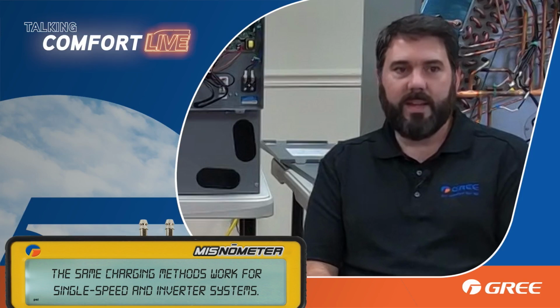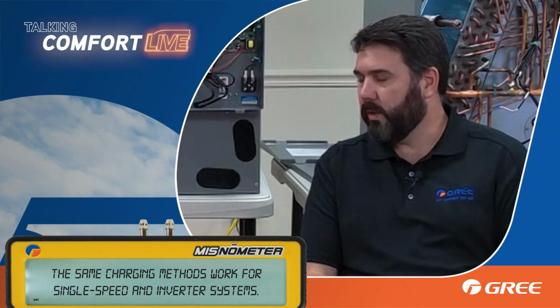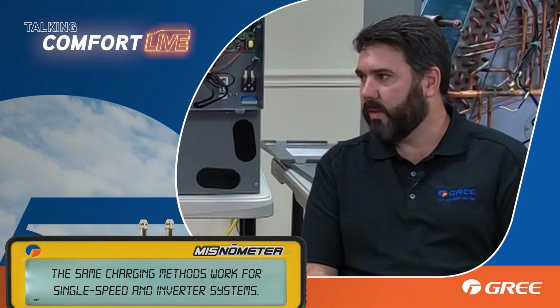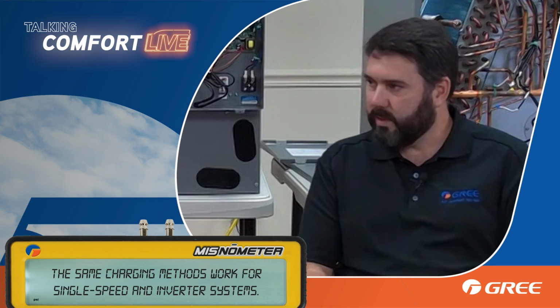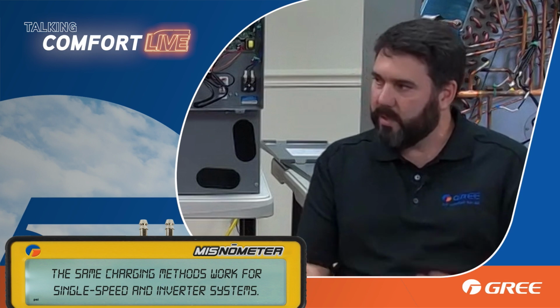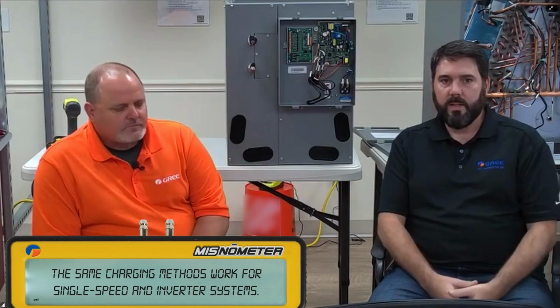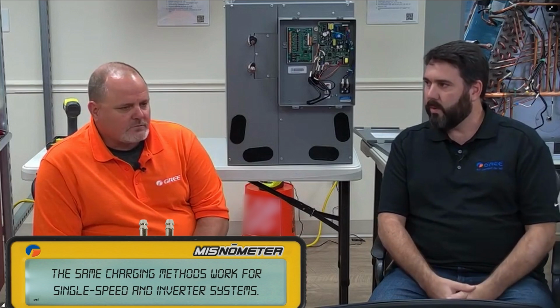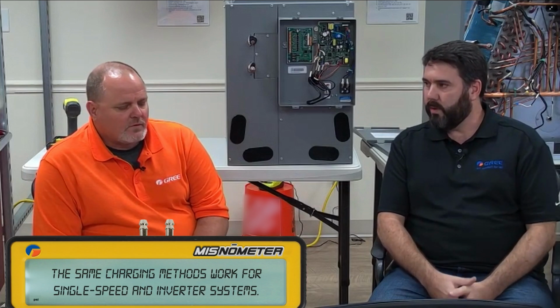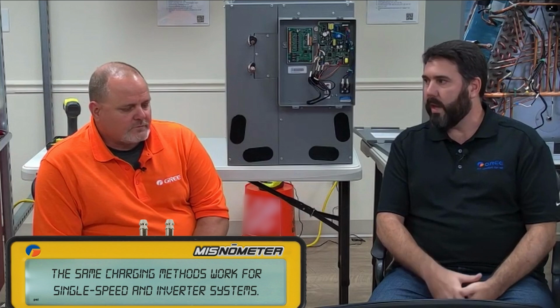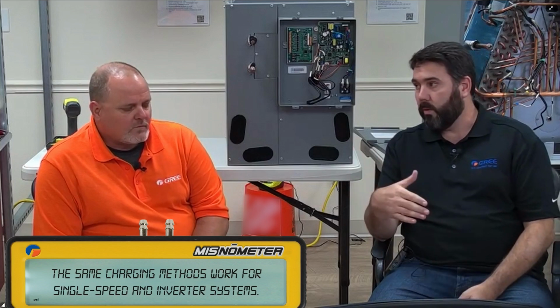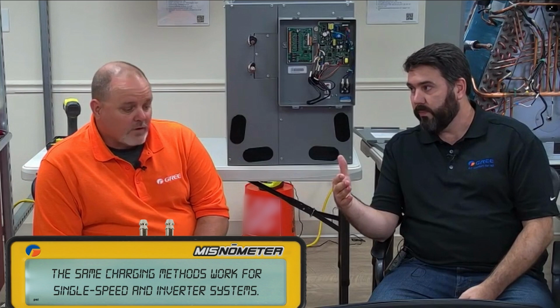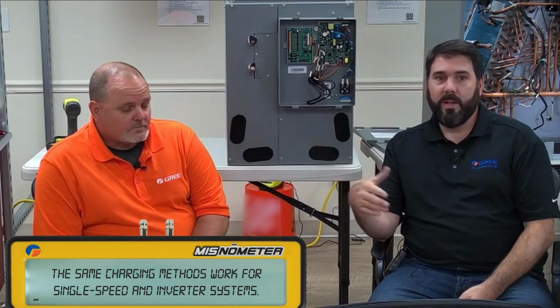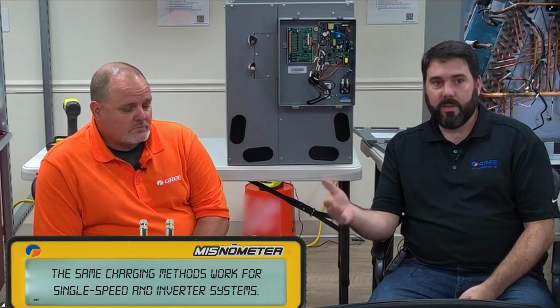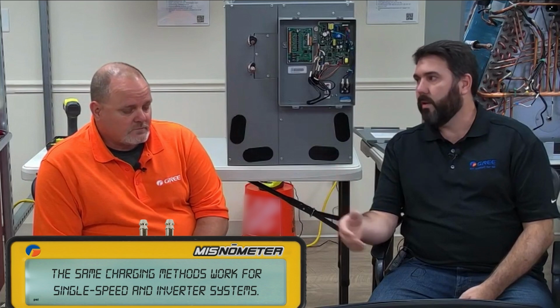But that being said, in cool mode, what are we looking for? Delta T from the supply and return, 20 to 25 degrees. So that's a good thing that you can check relatively easily without getting the gauges out to know that it's in a good spot with your charge. And then if you do have Delta T that's way outside of parameters, high or low, because high is bad too, right? Right. So high or low, then we need to go ahead, hook the gauges up, check the charge, see where we're at.